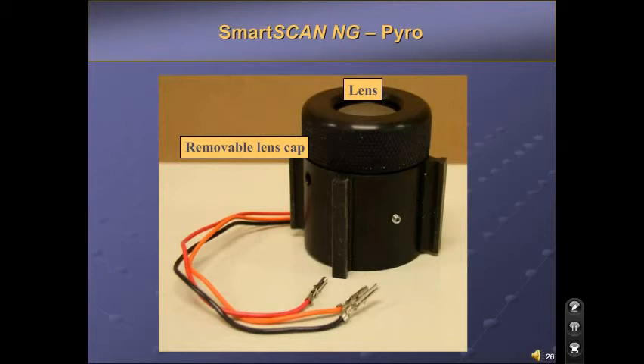Notice that, like the rail mount, the Pyro assembly has shock mounts attached to it. This allows shock absorption from many different planes and keeps the Pyro assembly very quiet, even in a high vibration environment. There are 2 screws in the sides of the Pyro assembly. These screws are set at the factory and should not be adjusted in the field. A periodic cleaning of the lens is the only maintenance required on the Pyro block. Cleaning is recommended about every 30 days. When cleaning, it is important not to overly scrub or use products that contain alcohol or ammonia. This can cause the coatings on the lens to be compromised.